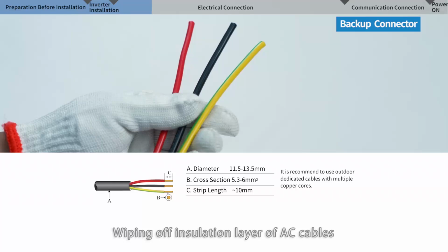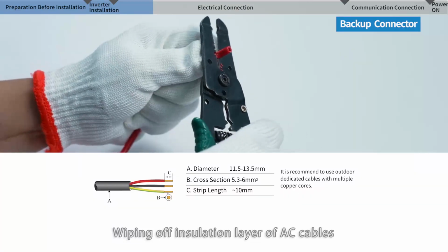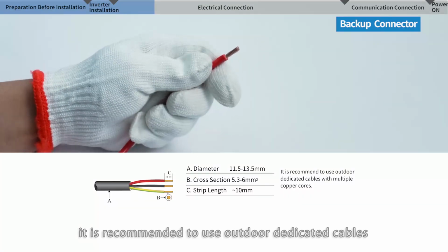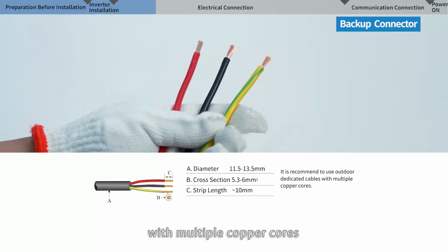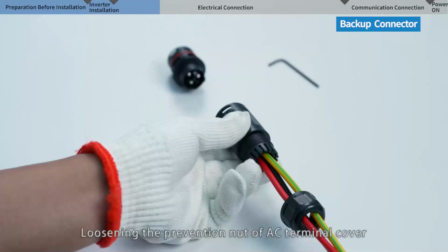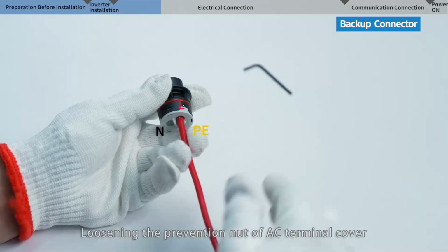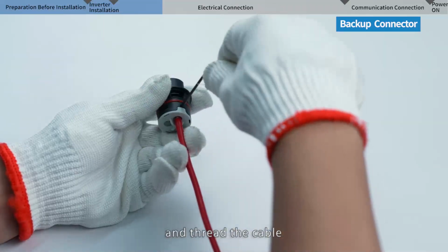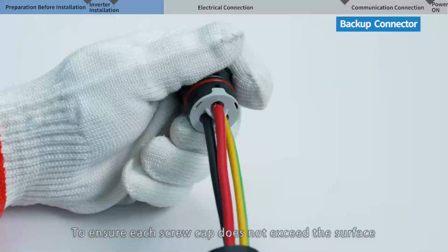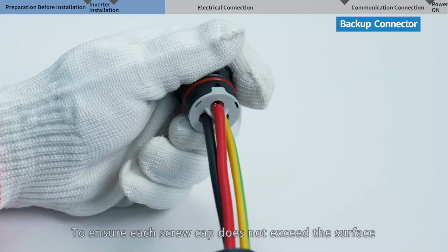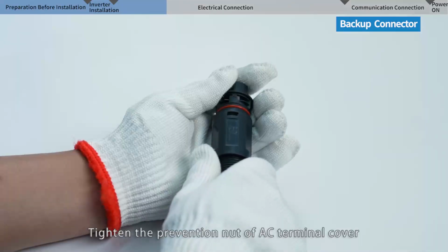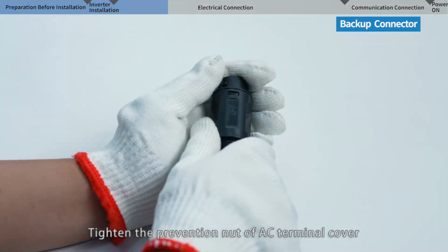Wipe off the insulation layer of the AC cables. It is recommended to use outdoor dedicated cables with multiple copper cores, cross-section 5.3 to 6 square millimeters. Loosen the prevention nut of the AC terminal cover and thread the cable. Tighten 3 screws to ensure each screw cap does not exceed the surface. Tighten the prevention nut of the AC terminal cover.